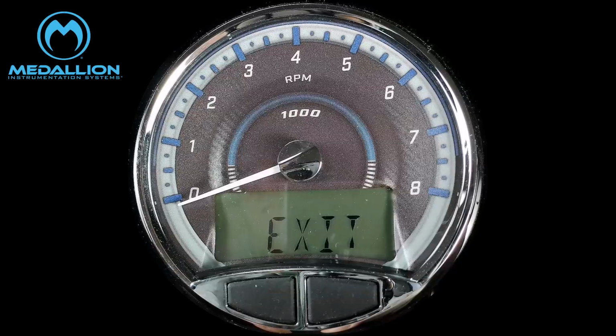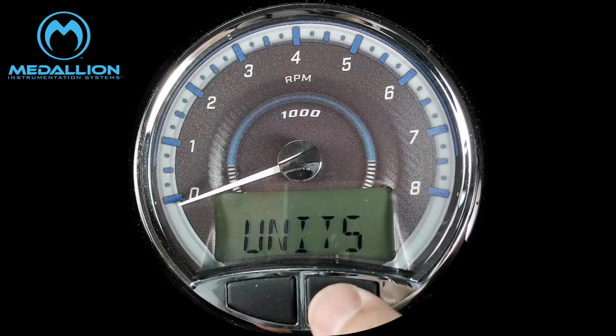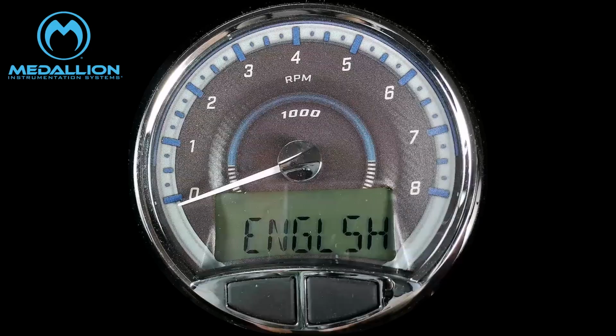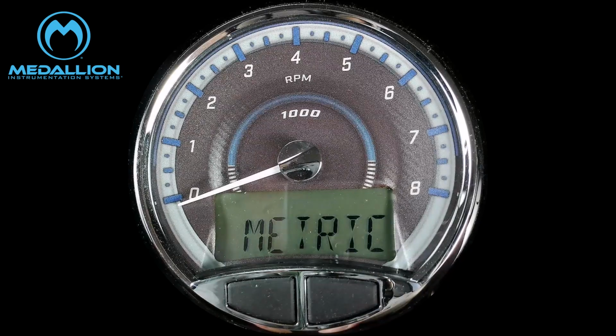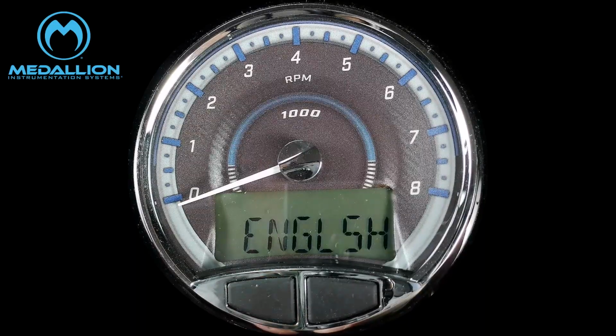To exit out of programming, go to the word exit on the list and then press the right button for approximately 1 second. This will take the display back to normal operation. To enter into the Units section, you will press the right button for approximately 1 second until you see English displayed. In the Units section, you will program the gauge to measure using the English system or the metric system. To do this, simply press the right or left button until the system you desire is displayed. Once it is displayed, press and hold the right button for approximately 1 second. When the display goes back to Units, then the gauge is programmed.